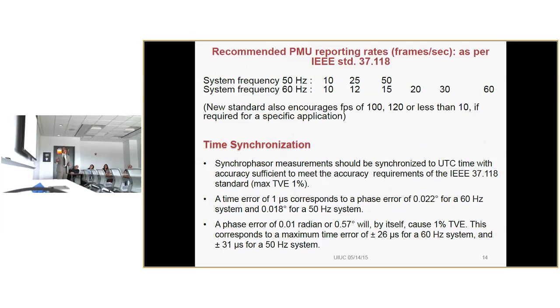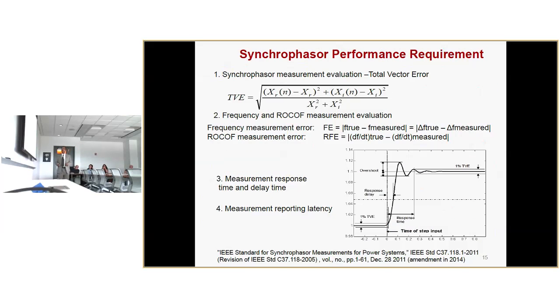And then it is synchronized to the GPS clock, as I said. And why a GPS clock? Why not an internet clock? An internet clock has an accuracy of milliseconds, whereas a GPS clock is accurate to microseconds. If there is an inaccuracy of up to 26 microseconds at 60 hertz, that itself causes a 1% error in the phase response. So that is why you need a very accurate clock.